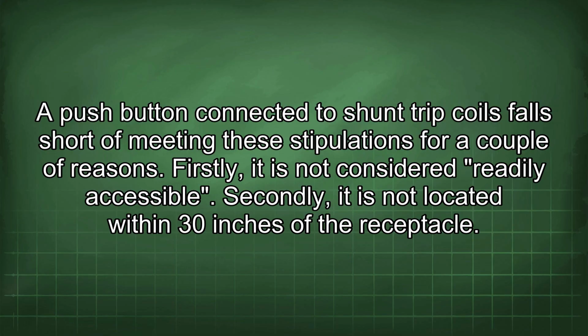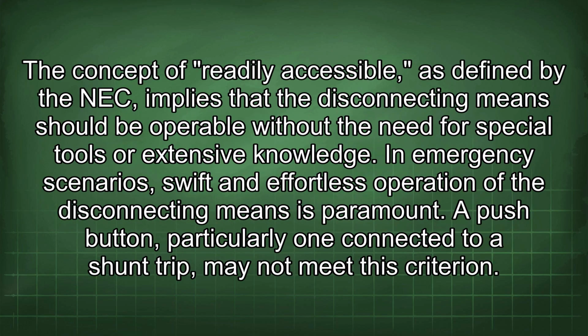Firstly, it is not considered readily accessible. Secondly, it is not located within 30 inches of the receptacle. The concept of readily accessible, as defined by the NEC, implies that the disconnecting means should be operable without the need for special tools or extensive knowledge. In emergency scenarios, swift and effortless operation of the disconnecting means is paramount. A push button, particularly one connected to a shunt trip, may not meet this criterion.